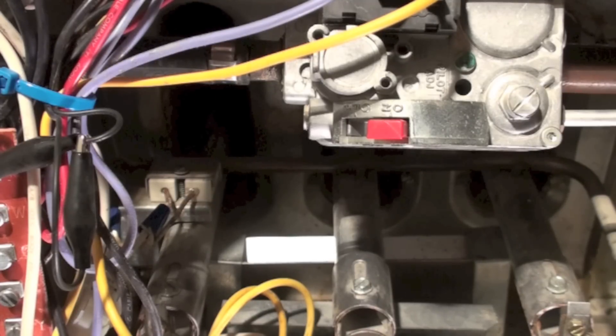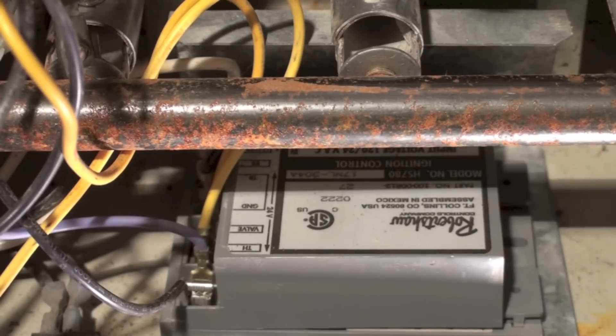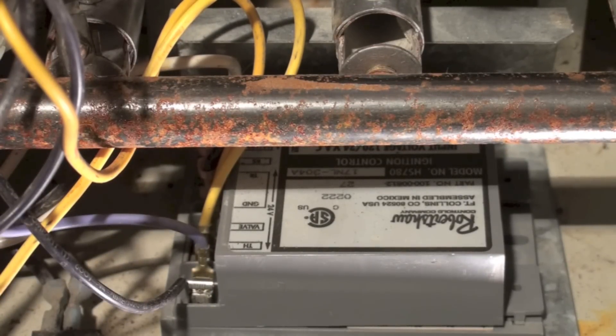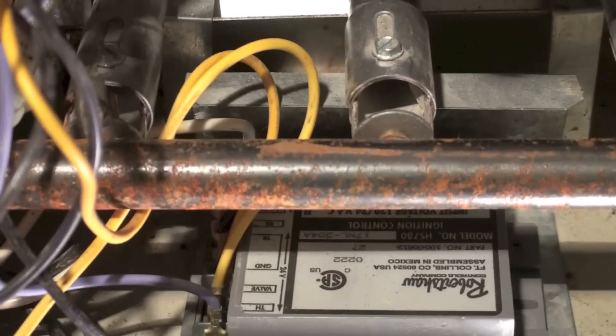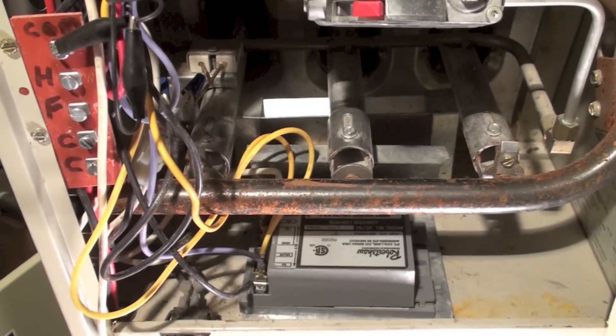The control right there is a Robertshaw HS 780. It doesn't have any lights on it that blink to indicate a fault or anything like that. We're going to try a couple of problems with it and see what we find. In order to tell if we've got power, one of the things that will work well is if I put a jumper across.